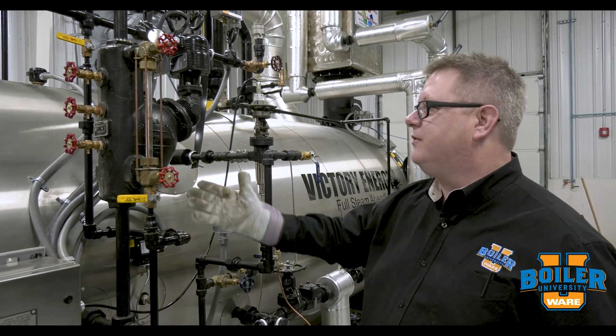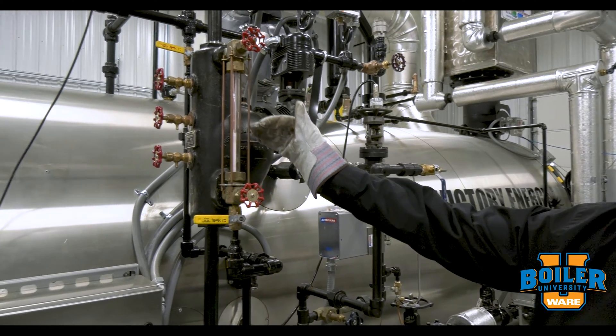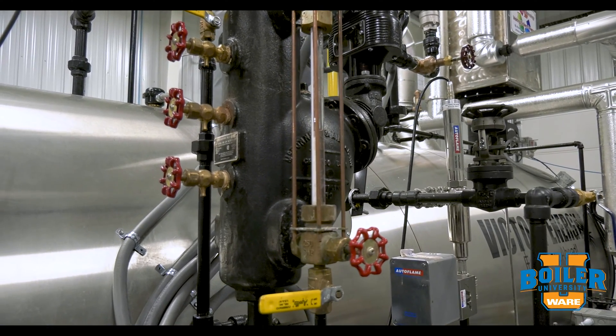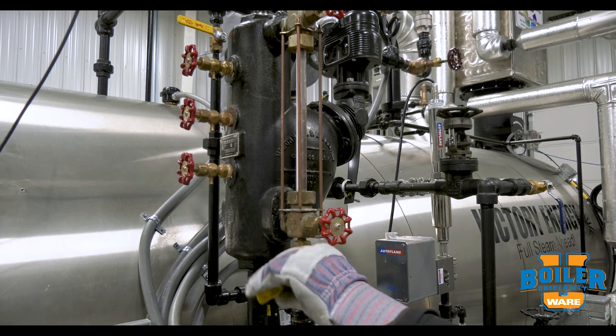This week's boiler tip we're going to talk about sight glass blowdown. If we don't see a gradual fluctuation of our water in our sight glass, or if we've got silt and sediment in our sight glass, we may need to blow it down. There's a blowdown valve for that, and we can open that valve to clear it.